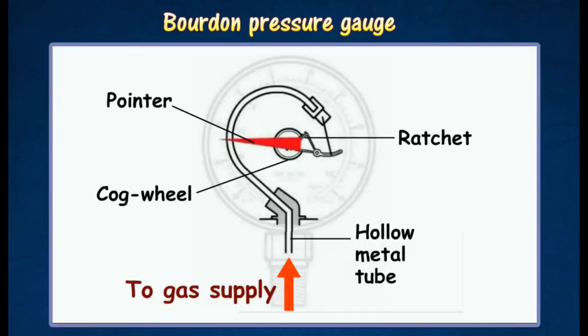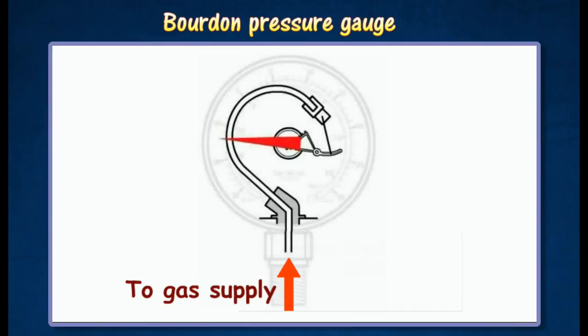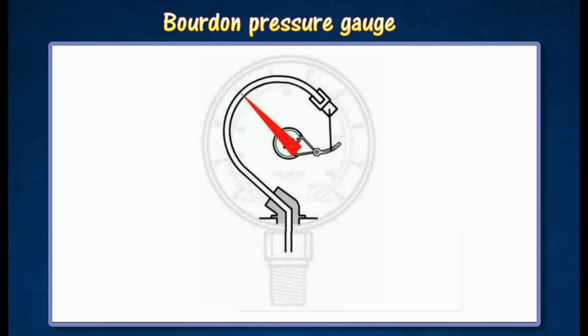When a compressed gas enters the curved tube, the tube tends to straighten out, thus causing the other closed end to move outwards. This movement is magnified by the lever arrangement, which turns the cogwheel that moves the pointer over a scale to indicate the pressure reading.